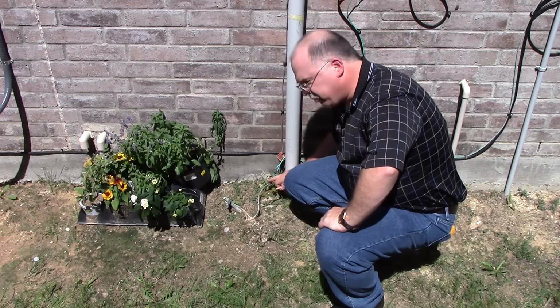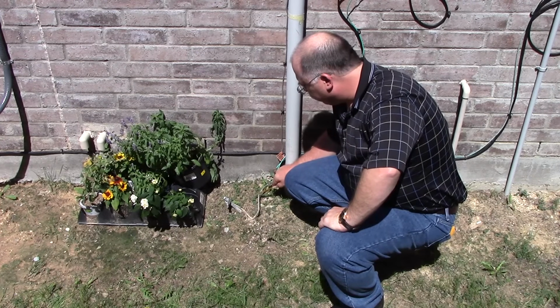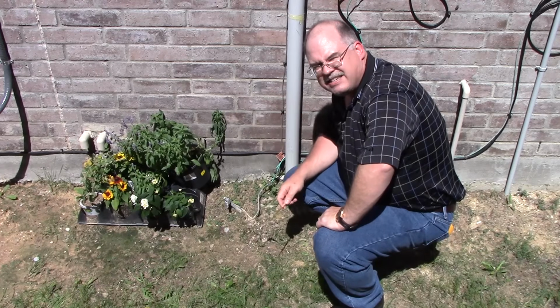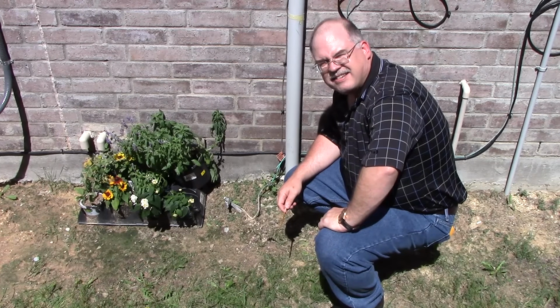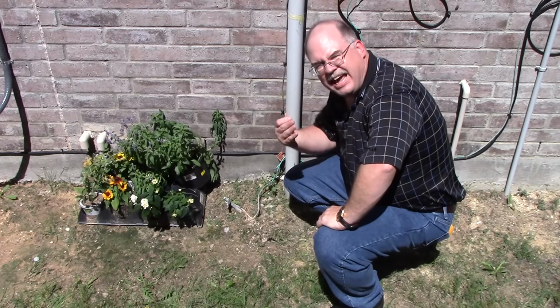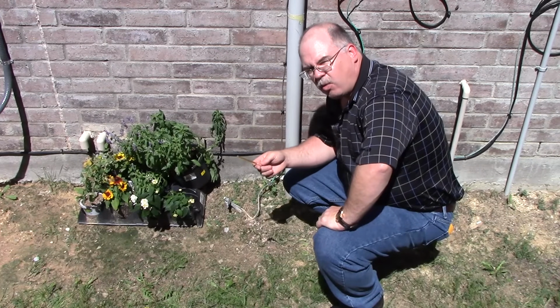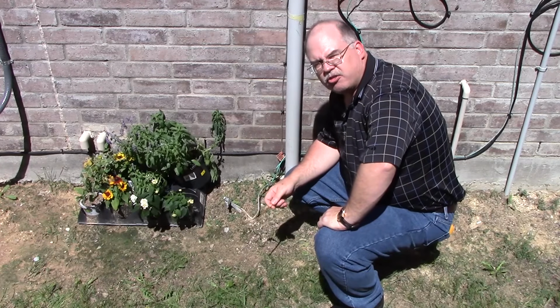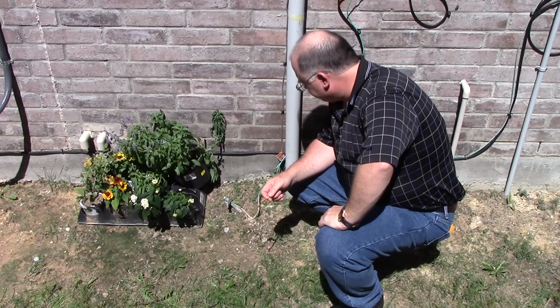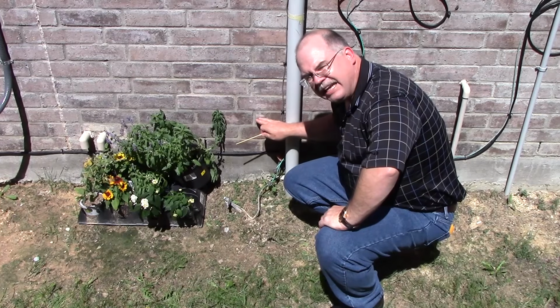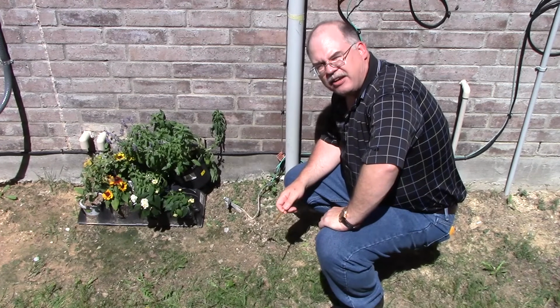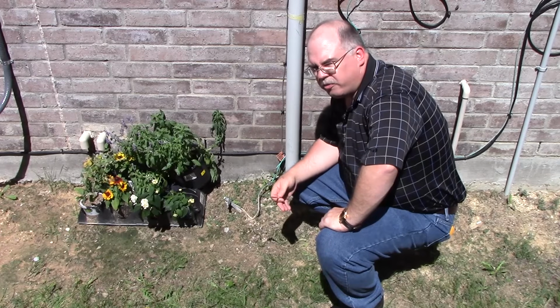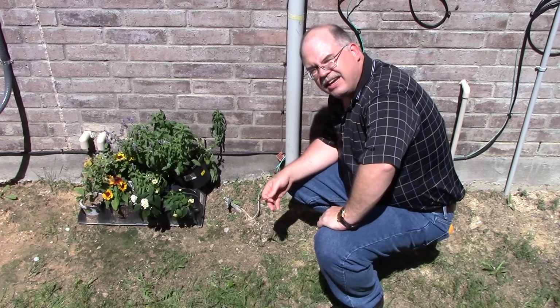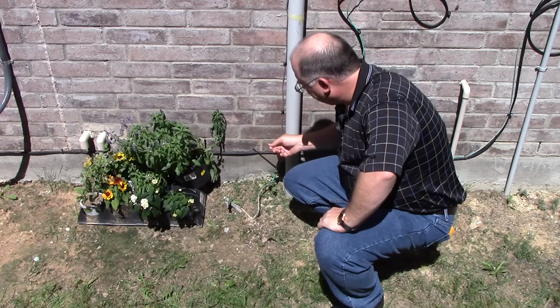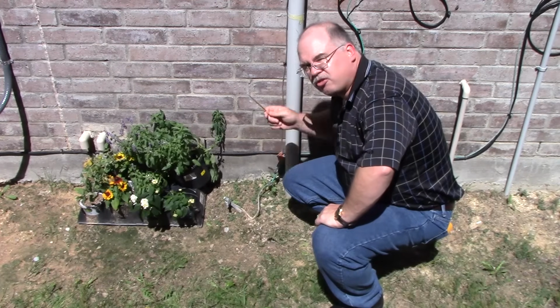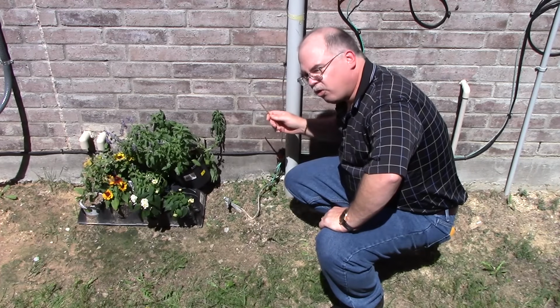Now, also, you'll notice some terminations here. Now, these terminations onto the grounding electrode conductor are for the TV system, the antenna, or for other communication systems. Now, under the new code, you're required to have a separate termination called the intersystem bonding termination point. So that intersystem bonding is required for all communication systems. It's not for use in order to make a connection to photovoltaic because it's convenient. It's only for communication systems. Okay, and that has to be mounted here on the outside at your service equipment, at your meter, in order to be able to make those connections.